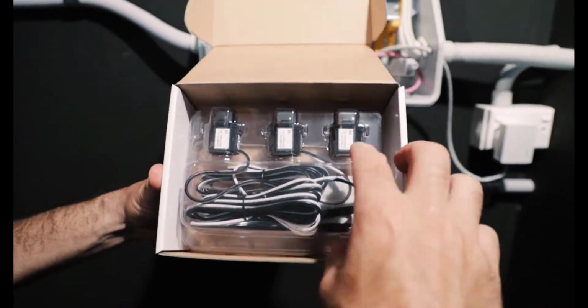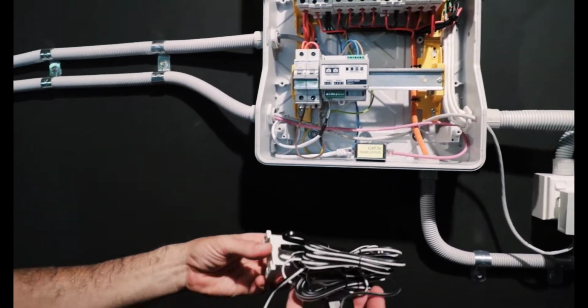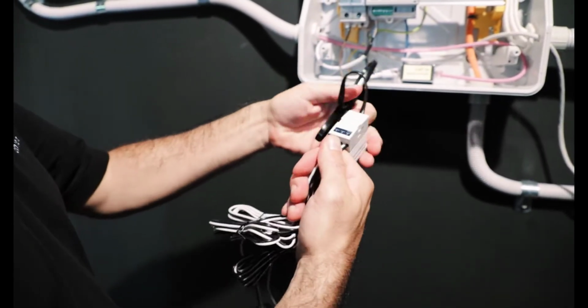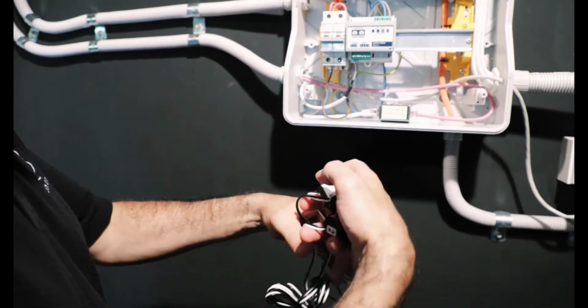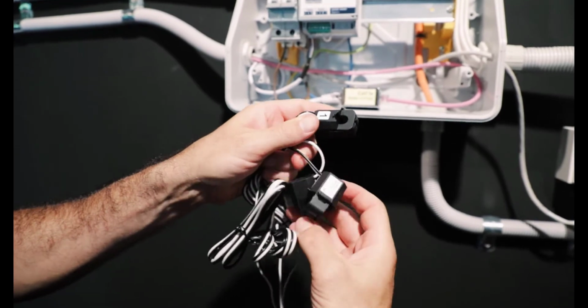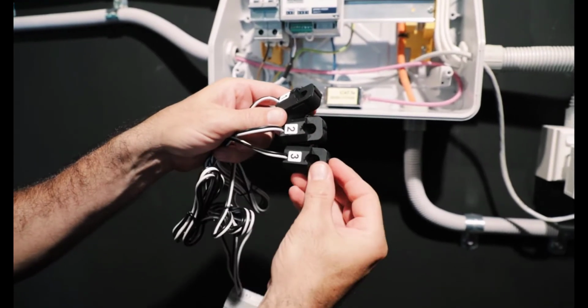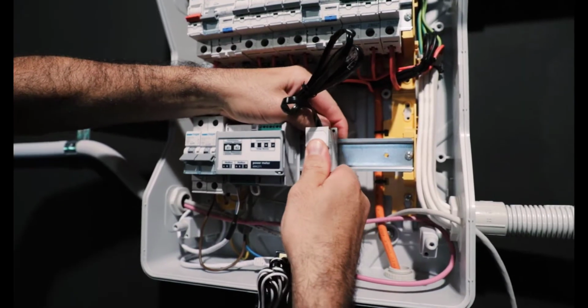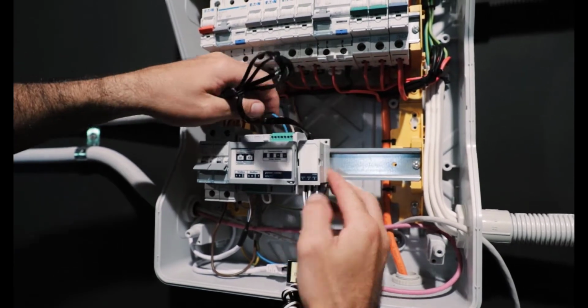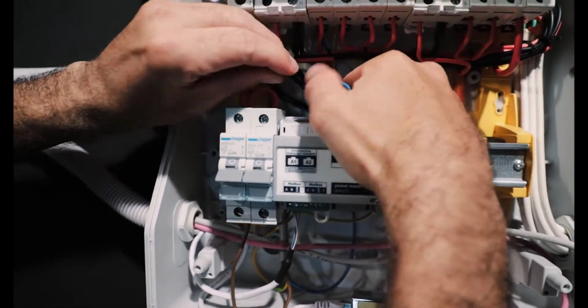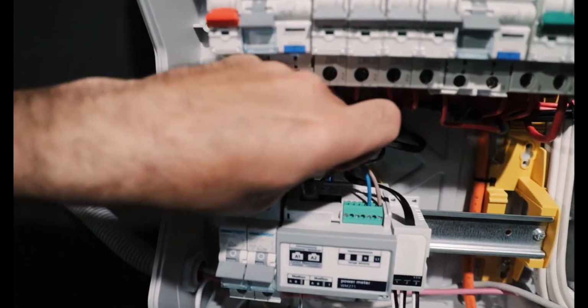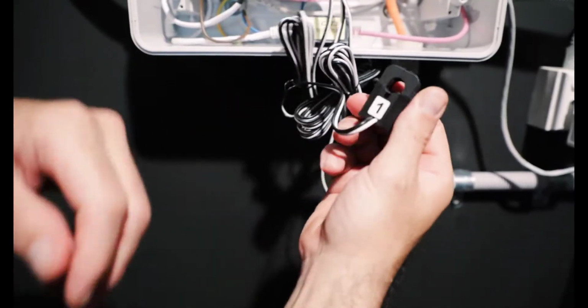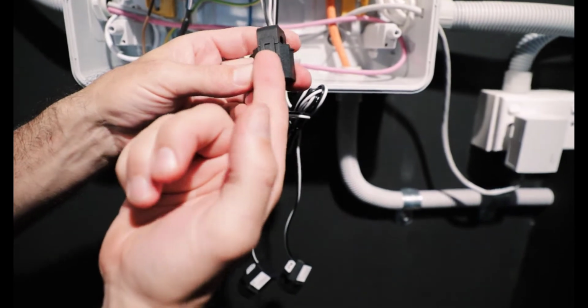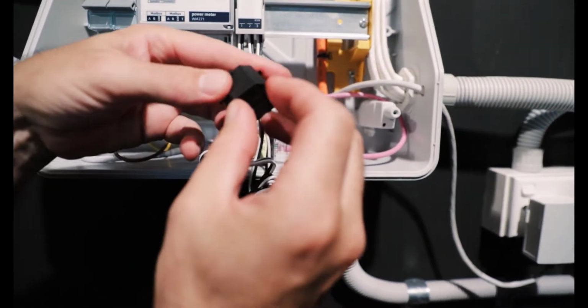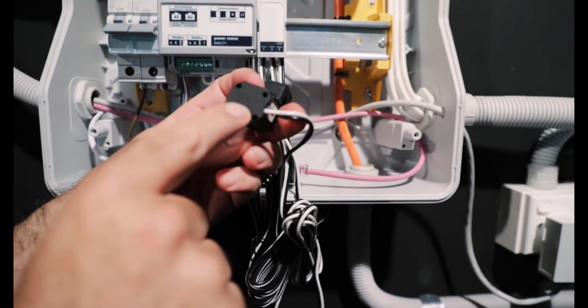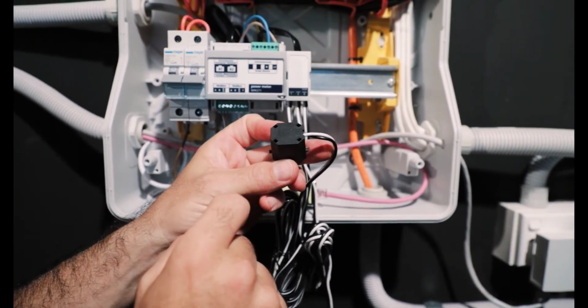Now all of the sonnen systems come with the same amount of CTs regardless of whether they're three-phase or single-phase, because like I said previously, you can install a single-phase system onto a three-phase property. So although we have the three CTs, they're clearly numbered, 1, 2, 3. So for any single-phase installation, we're only going to worry about CT number 1, which is for single-phase. Plug the transducer, which comes with that little black connector, into the A1 port. Then we take CT number 1, open it up. They are directional, there's a little arrow, so the power flow always goes out towards the cable. That's the easiest way to understand it. As you can see, the little arrow there.